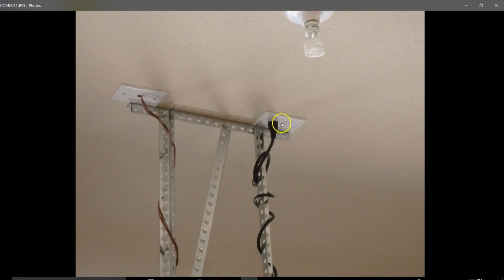This is your garage door opener outlet, and it's supposed to be GFCI protected. It even has a sticker on there, but it's not. Is that just swapping the outlet? In this case, probably not. It's going to probably take more than that. It's an electrical thing. It has to be wired to the box that way.